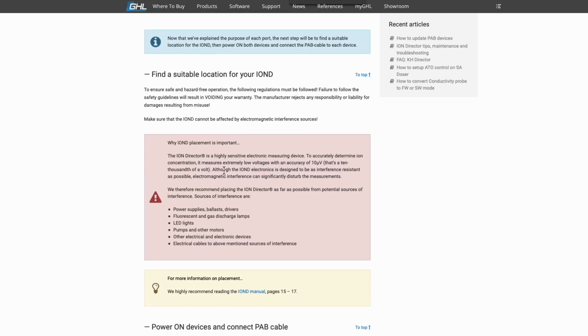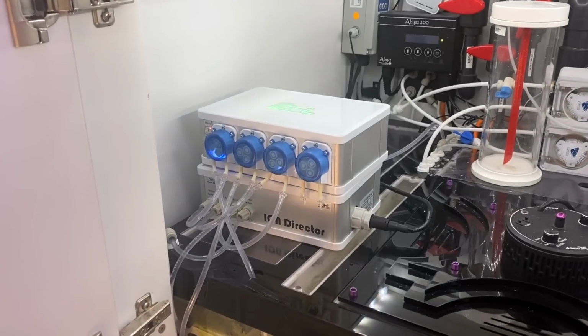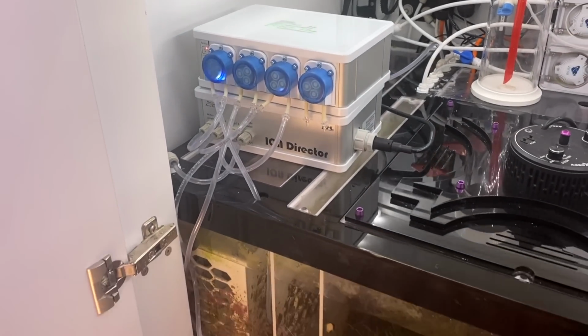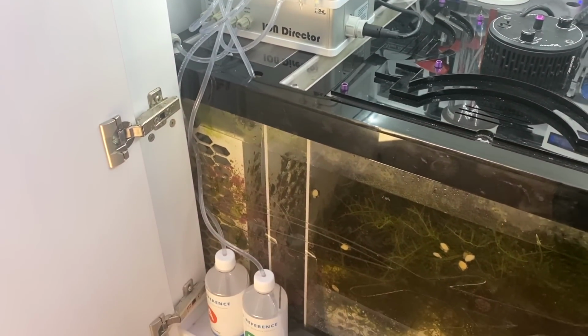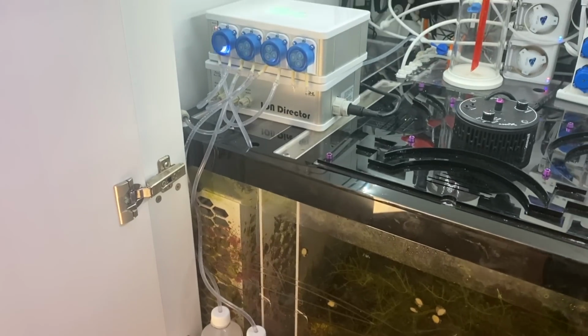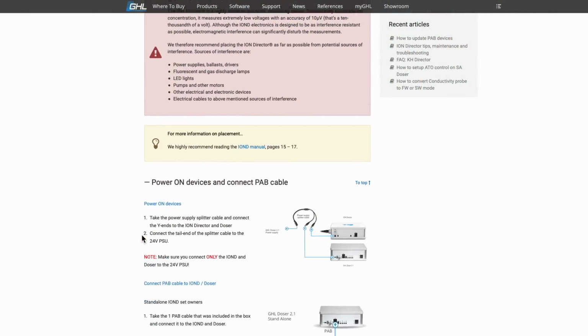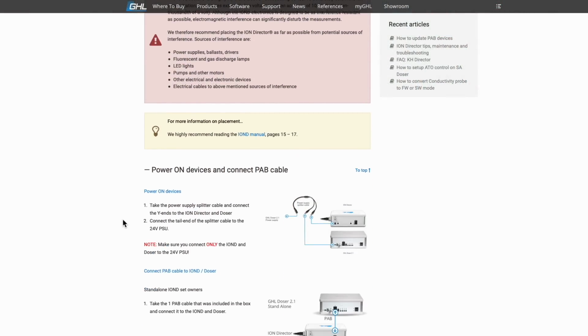Now, it does say that it is important that it needs to be away from things like power supplies and ballasts, because it could get electrical interference. So I found a pretty good spot on my sump, which gives me good access to water, a good spot to set the reference fluids, and away from any sort of interference it should get. Now, funnily enough, I did find this next step interesting.